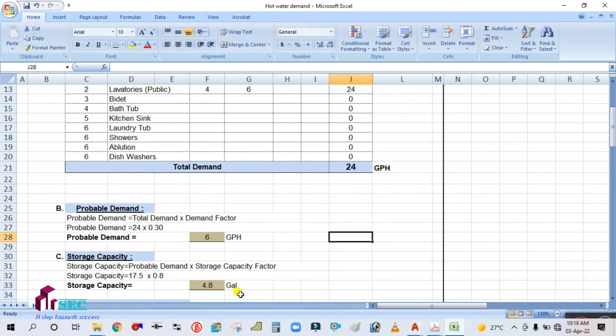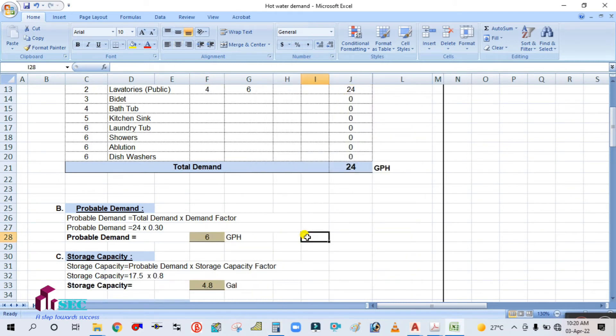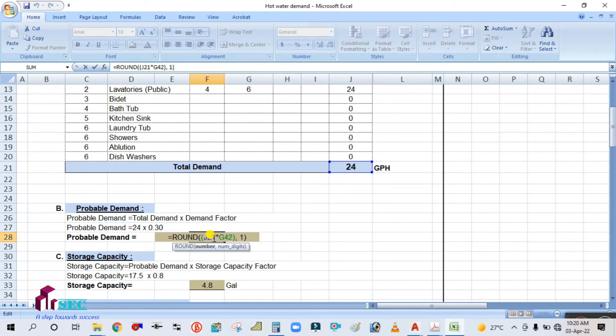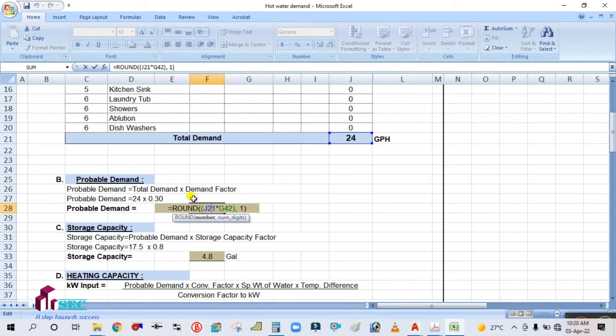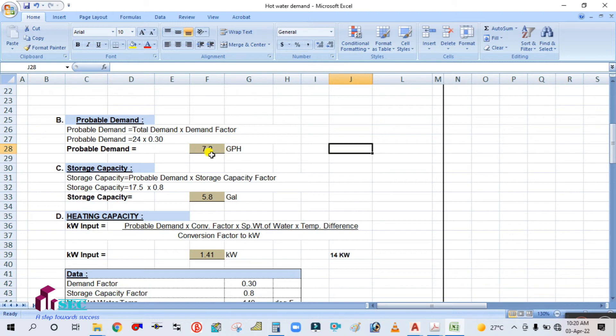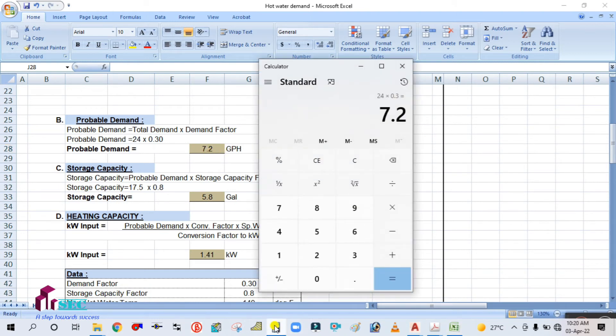So: 24 × 0.30 = 7.2 GPH. The probable demand is 7.2 GPH. This is already built into the formula in the spreadsheet, so simply change the demand factor value to 0.30 and the formula applies automatically, giving you 7.2.